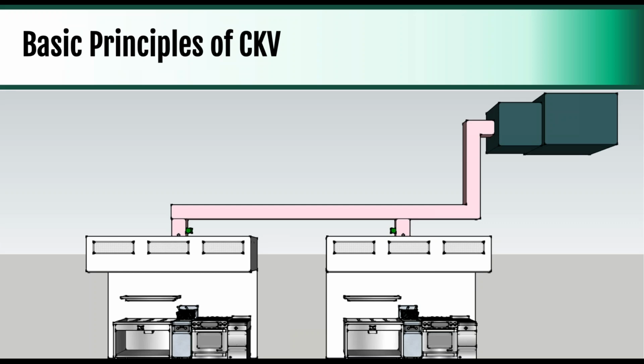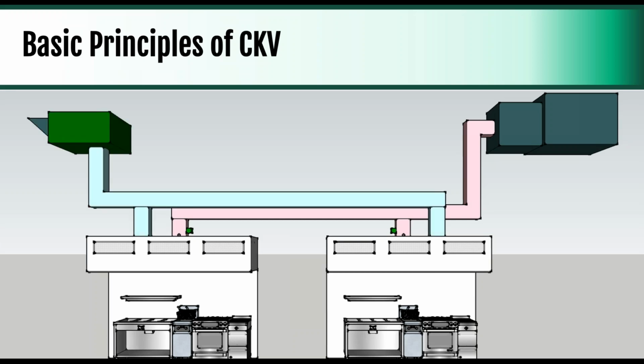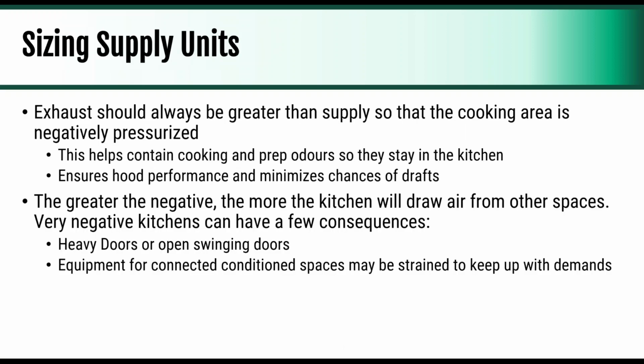In this example, I've got a filtration unit on the end, but it could easily be just a mushroom fan. But anyone who's been working on this knows that if you're just exhausting a lot of air and not bringing anything in, you've got a really negative space. You're not going to be able to open doors, and things aren't going to work properly. So that's where the supply air comes in. And that's bringing in fresh air, tempering the fresh air in almost all cases. Certainly in Canada, it's going to be heated and in a lot of cases cooled to replace all that air that's being exhausted. So sizing supply units is one thing we get a lot of questions on.